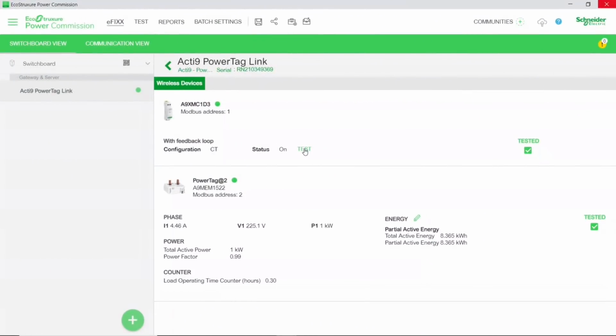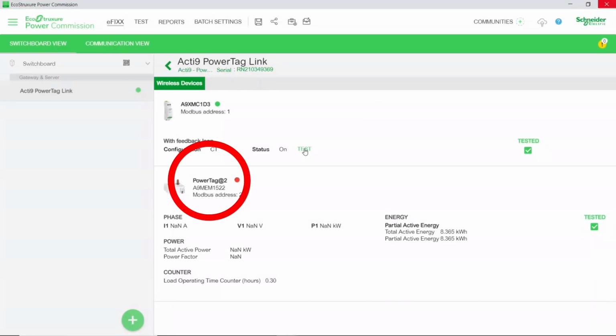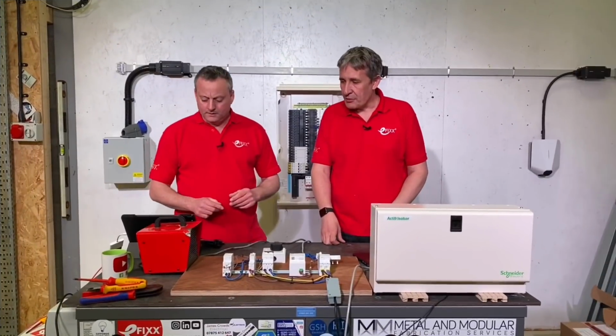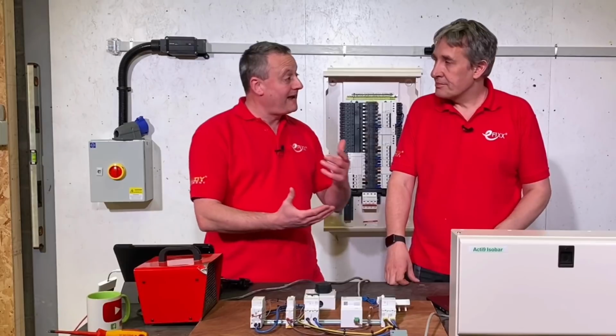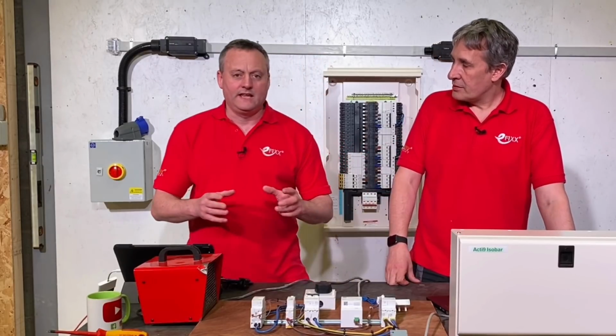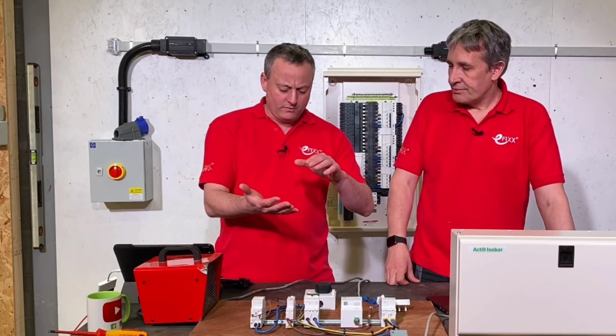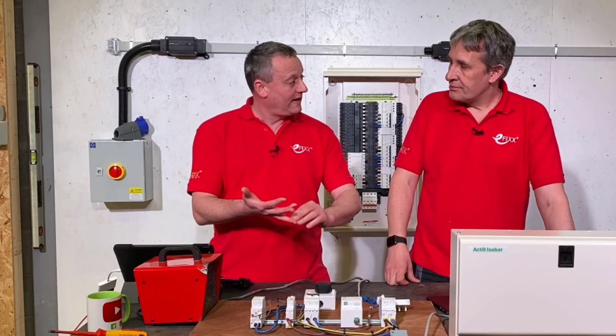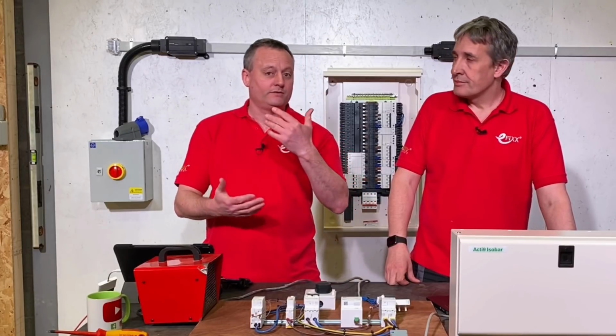You'll see the PowerTag go from green to red on its next update, about 30 seconds. That came quick - you can see we've lost voltage, and there's no power recorded now. So I could be back looking at this management system, and before I even go to site, I know which breaker has tripped, I probably know its location, and my fault-finding process has already started.